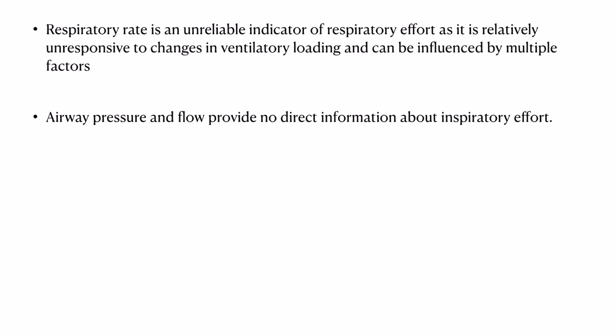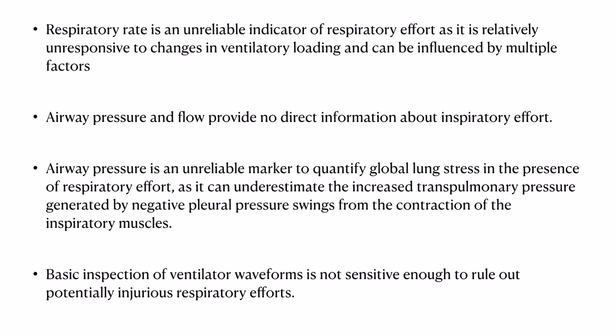Other things that we see on a ventilator are the airway pressure and the flow, but they do not provide any direct information on the inspiratory effort of the patient. They provide more information regarding what the ventilator is delivering. Airway pressure is an unreliable marker to quantify global lung stress in the presence of a respiratory effort, as it can underestimate the increased transpulmonary pressure generated by the negative pleural swings from the contraction of the inspiratory muscles, especially when the patient is breathing on a spontaneous mode. Basic inspection of the ventilatory waveforms is thus not sensitive enough to rule out potential injuries from the respiratory effort of the patient.